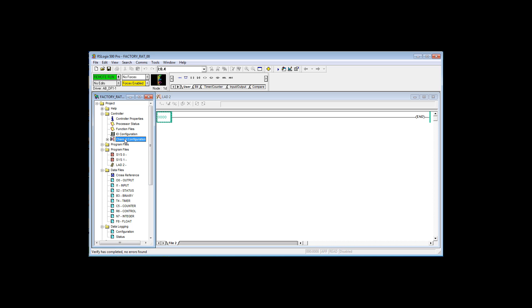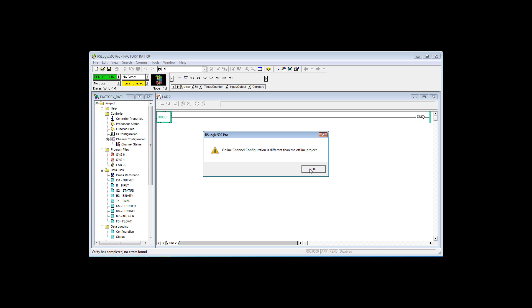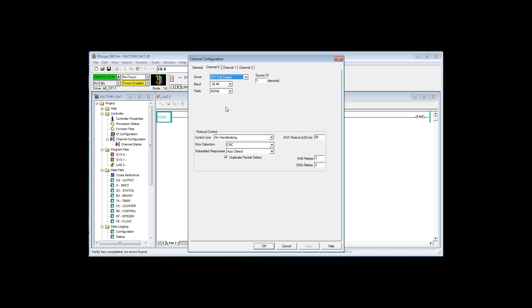I'm going to go to channel configuration. It says that the online channel configuration is different than the offline project. We know that. Channel 0 is 38.4 the way we set it. Channel 1 however is not 86, it's 227. Now what you don't know about these four values here is they are octets. They are 8-bit binary values. So 100 100 100 227, that's 8 bits, 8 bits, 8 bits, 8 bits. The address of the network, the whole network as a whole, is 100 100 100. We know that from the subnet mask, which I'll explain later. Then the address of this PLC on the network 100 100 100 is 227. And there you have it.